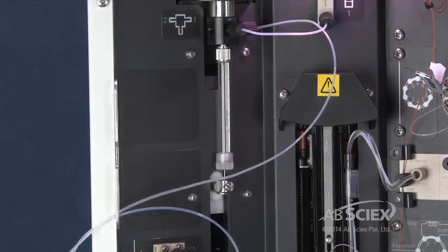The syringe will wear over time, requiring replacement. However, do not assume that the syringe needs replacement because there are air bubbles observed in the syringe. Air bubbles can simply mean that there is a restriction somewhere in the aspiration path. If the syringe requires replacement, it can be replaced by first...